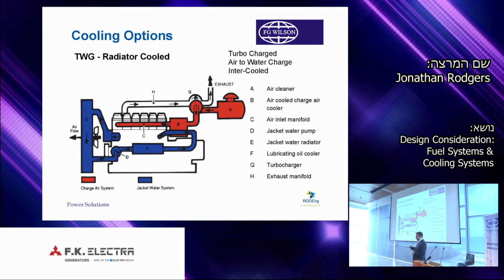We have, in the 12-cylinder range, from around 1100 kVA up to 1500 kVA, the option with the TWG, and this is basically where the charge circuit has an intercooler mounted within it that then discharges the heat into the jacket water circuit, and then a single core radiator is used to cool both circuits.